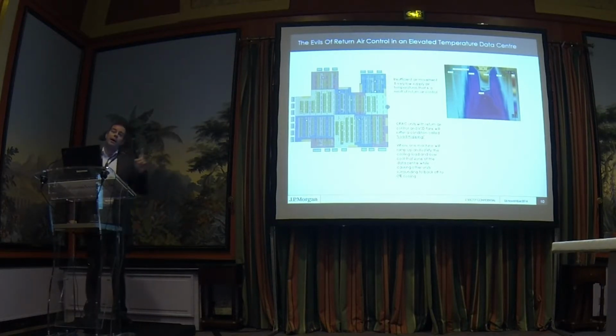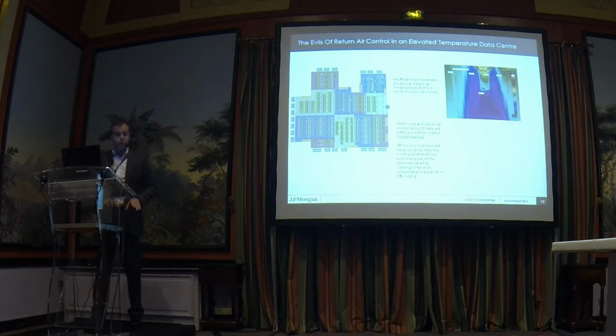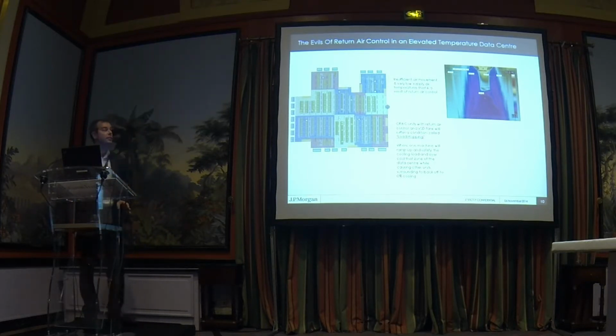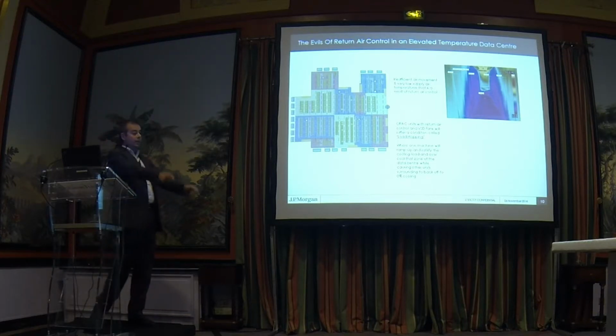And then you go again, and you go back again, and then you'll find other tiles that you push too much air, you shut them down again. So you end up with a condition where everything in your data center should be about 75%, maybe around there. But then knowing that you've got that extra capacity, what will happen is the pressure under the floor will begin to levelize out. Instead of having 4, 5, 10, 15 Pa of pressure there, and you've got about 1 here, you'll find that you'll probably end up with about 8 or 9 Pa across the entire floor area of your data center. So the moment you land a new piece of kit in, you can go up and open it up a bit more, and you know you've got the air there.